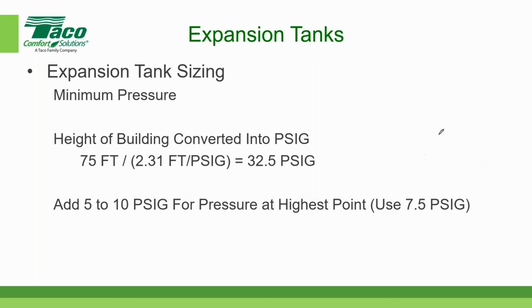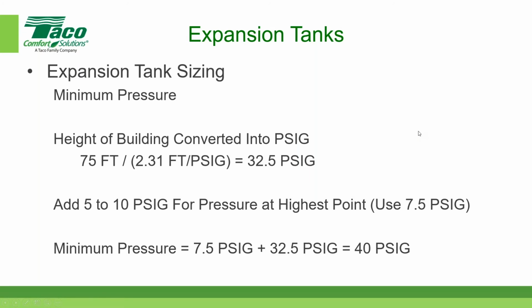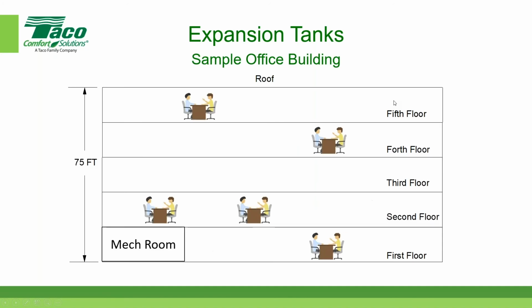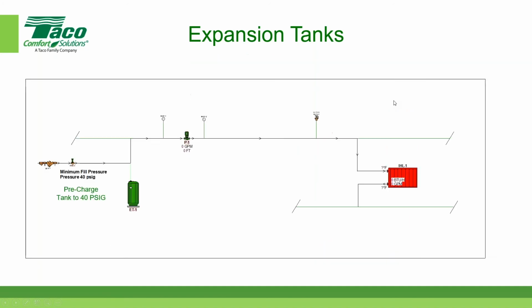And if that's the case, then the pressure at the bottom of the building is going to be that 7.5 plus 32.5, and that's where the 40 PSIG came from, and that is the minimum pressure at the expansion tank. Okay, so we just decided what the minimum pressure is at the expansion tank, and I want to emphasize that, so I'm circling the minimum pressure.